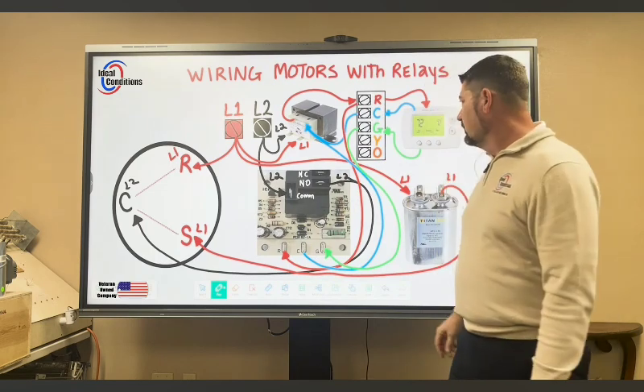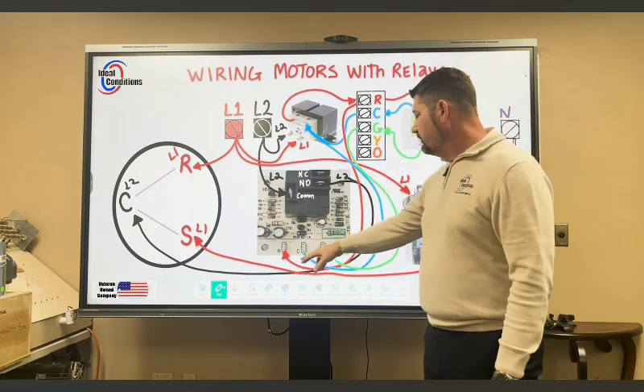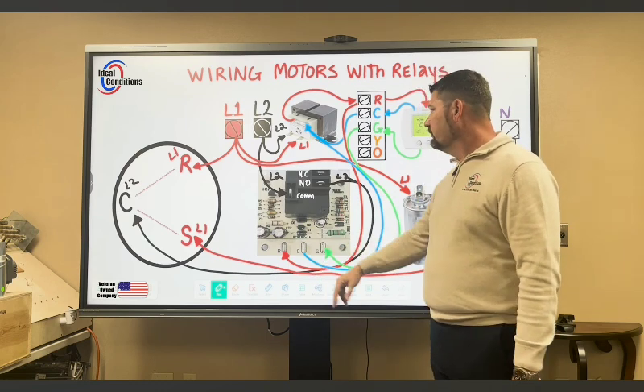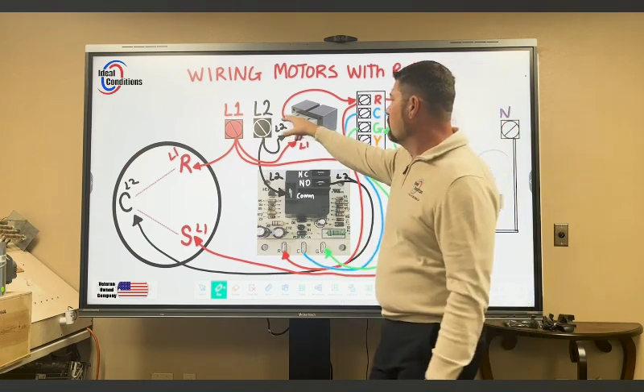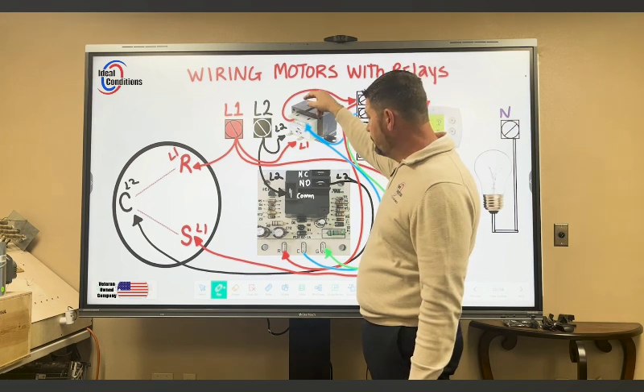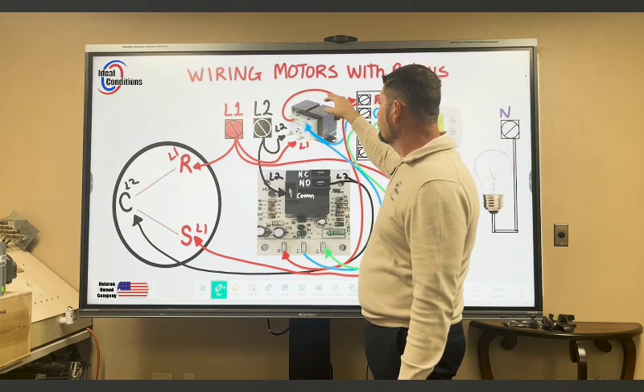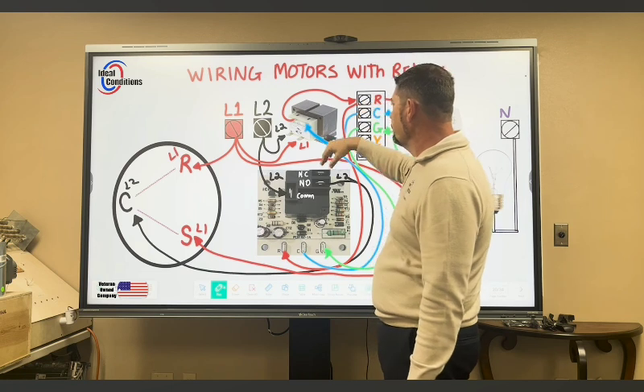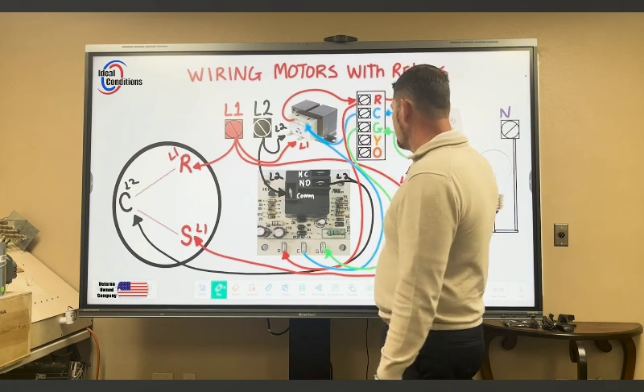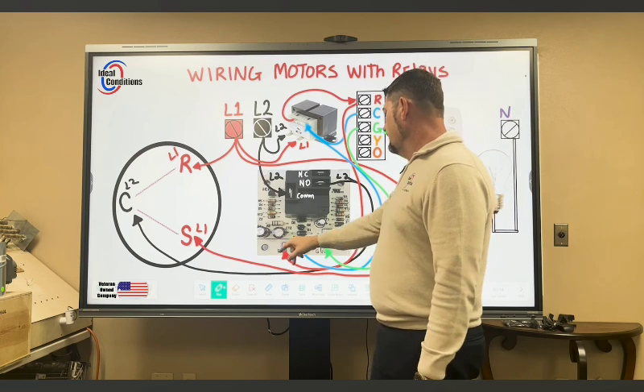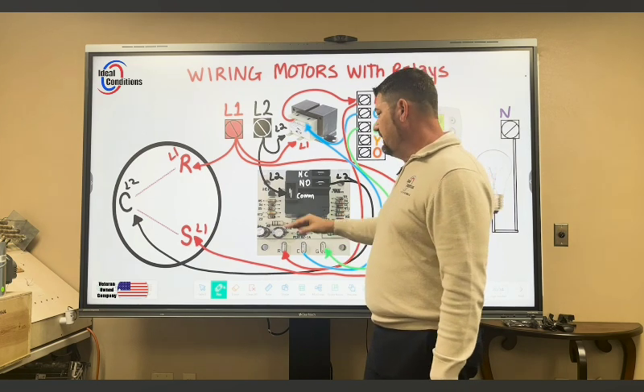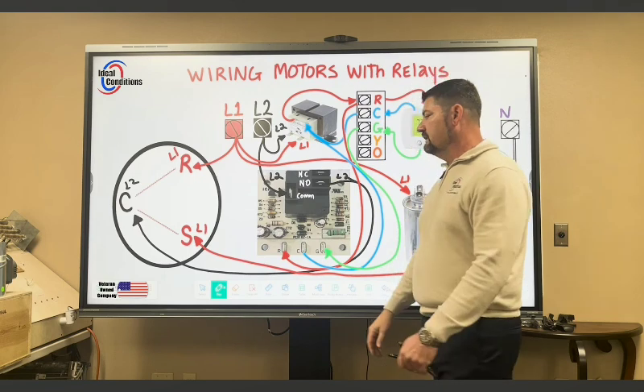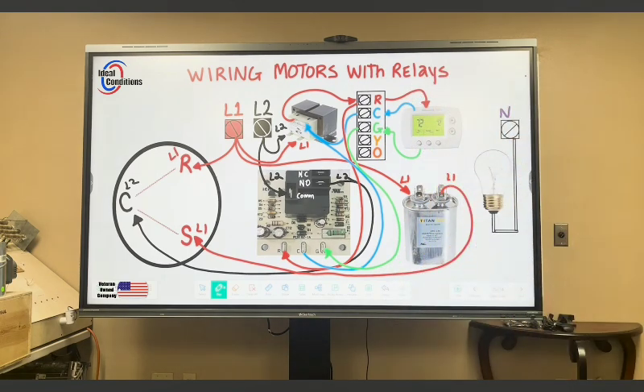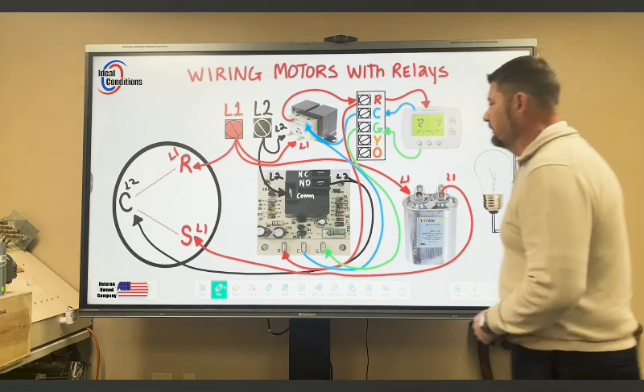Now, if you wanted to break any one of these, you would just break your red here through the float switch. Actually, if you come out of your transformer, you should go into your fuse, out of your fuse, into your float switch, out of your float switch to here. This way, if your float switch trips, you lose power on the thermostat. Even if this was on an off delay, it immediately shuts off, so everything's just down. Nothing can come back on. That's pretty much everything that we need to go over on this.